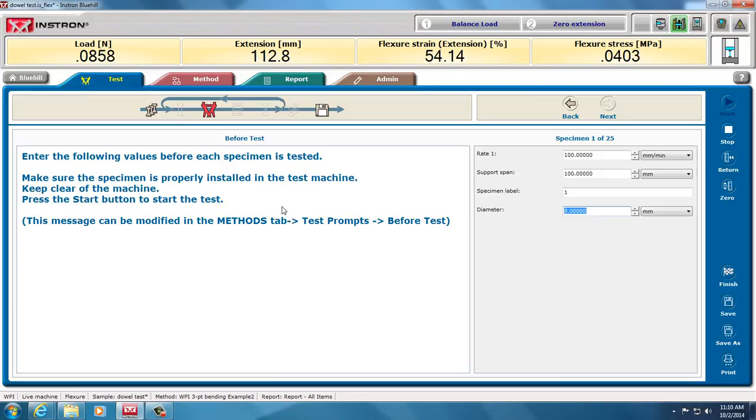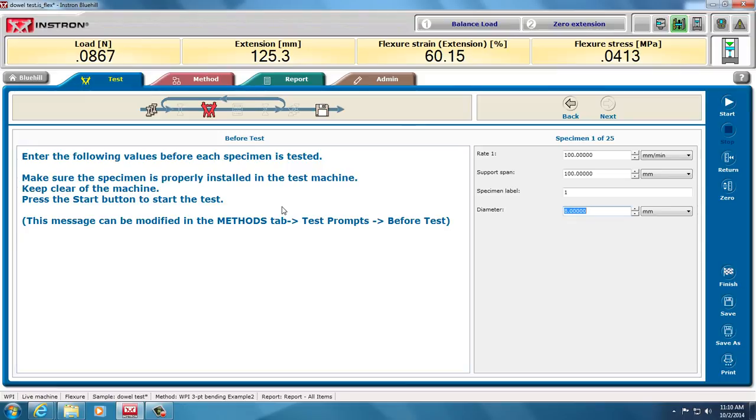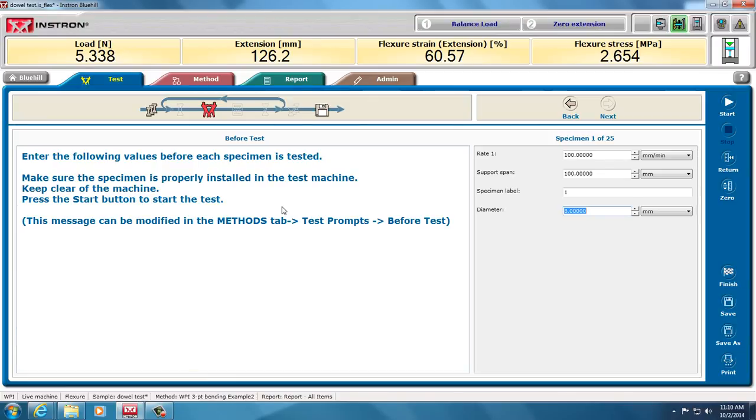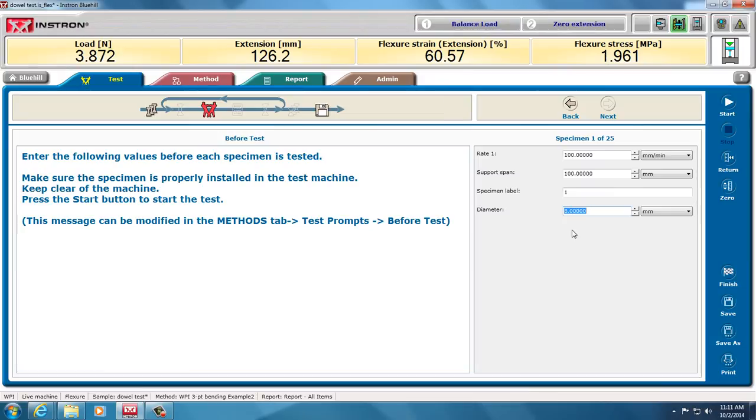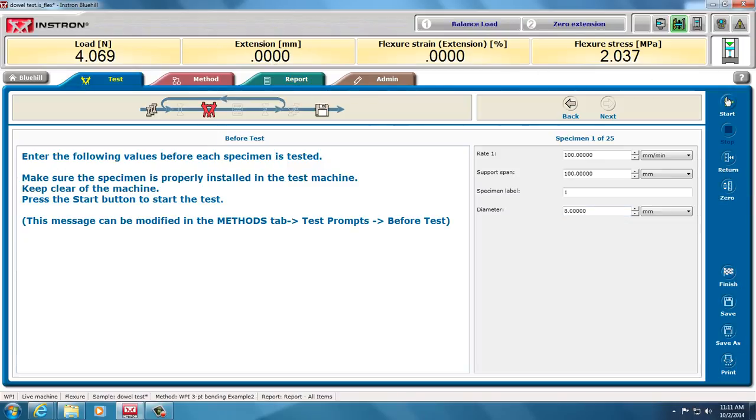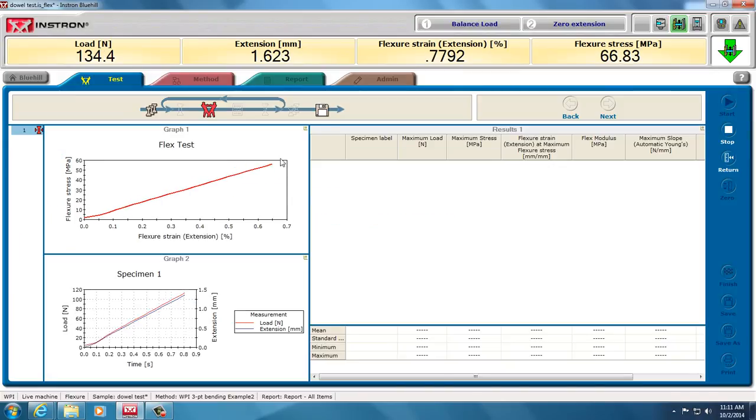Before I do this test, I need to put my tare load on. Bring my sample, the anvil to my sample. Put a small tare load on. I'd like to start with about five newtons since it's a 2000-newton load cell. And I need to put my safety shield in place to make sure my safety stops, my mechanical stops, are in place also. And then I'm ready to start my test after I zeroed the extension, either up here or here. And I'm at zero extension at my tare load. And I can start the test.